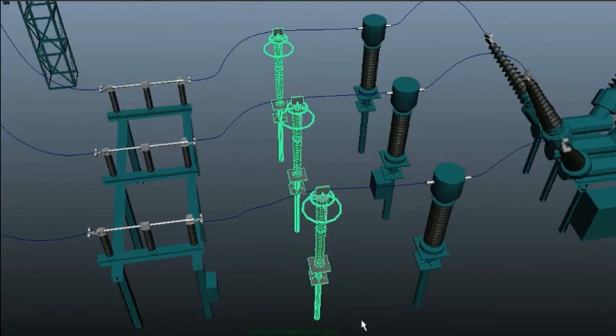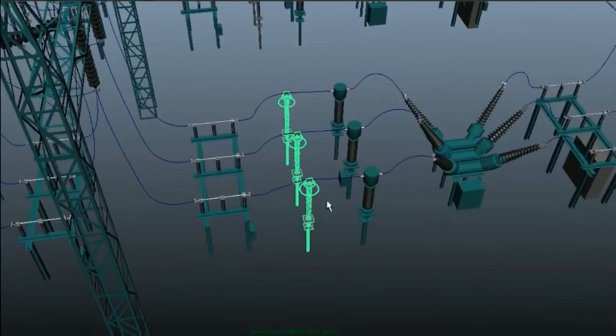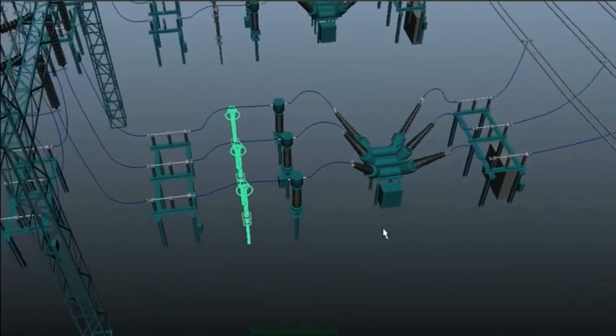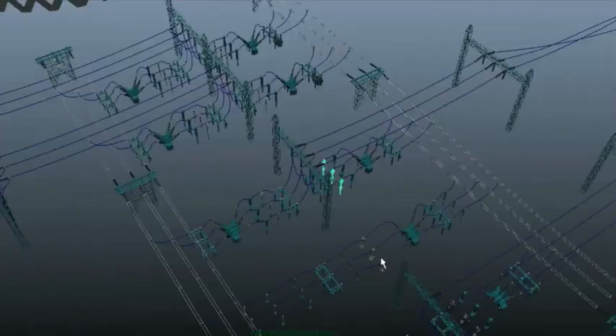The current and voltage transformers installed at different places in the system not only measure the value of current or voltage in the respective line, but also give input to the relays, which detect any abnormal change in their value and operate the circuit breaker to take preventive action and therefore protect the complete system. So this is about the double bus arrangement which our power plant switchyard generally consists of.